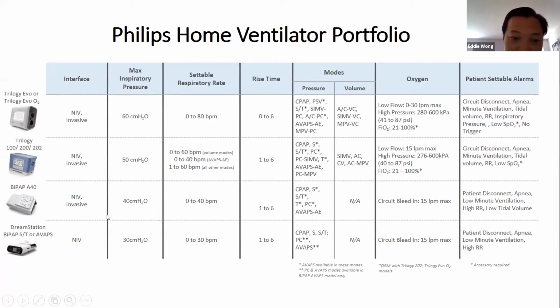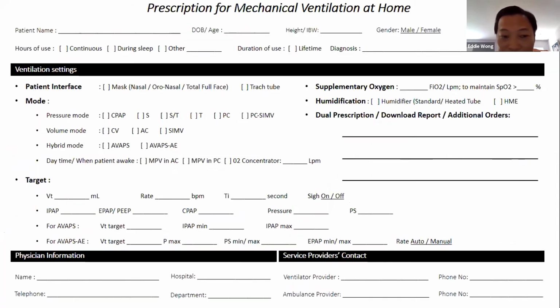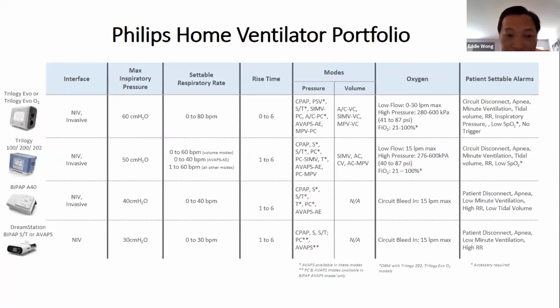For ALS patients, normally you do not require pressure more than 30, especially when you use a mask to perform mask ventilation. Any mask on us, when we set the ventilator, if you try to set up to 30 cm, you feel very discomfort because the pressure is too high. Unless you're using an invasive ventilator, then you need higher than 30 centimeter water of pressure. Okay, so that's why 30 cm is more than enough.